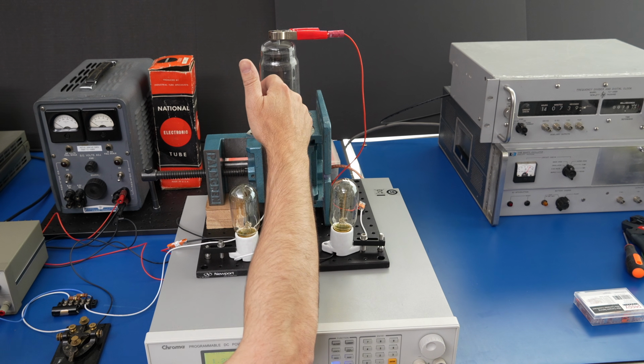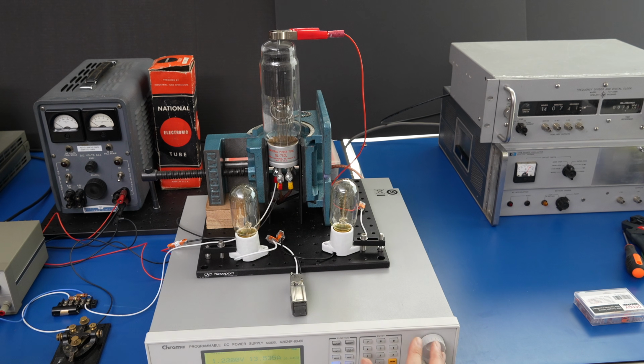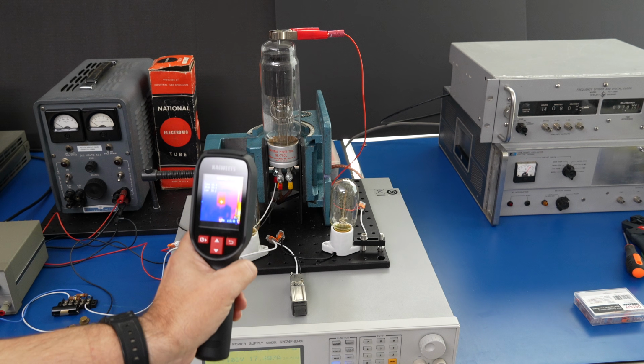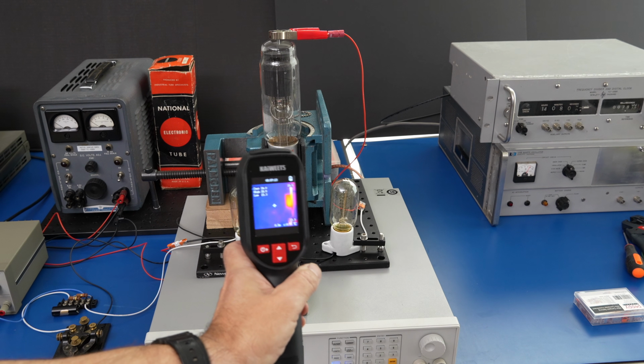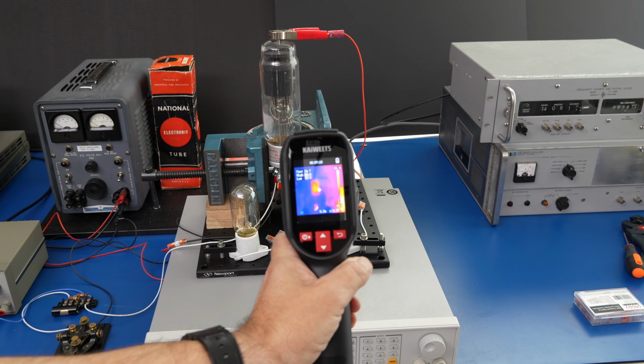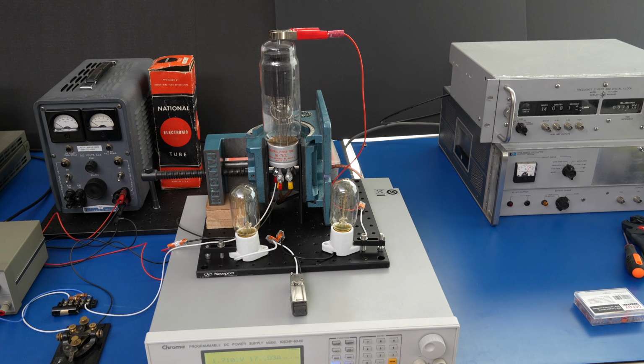Alright, so it's starting to heat up, and I see the mercury starting to evaporate. 18 amps, you see it? No. Oop, there you go. So we have a hot tube finally. What happened is that I was so low, it didn't heat up, and the resistance of the filament never increased.